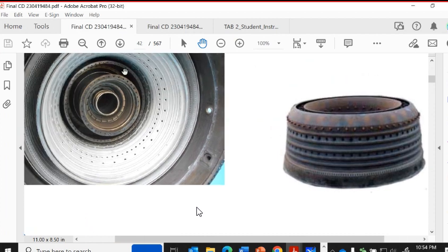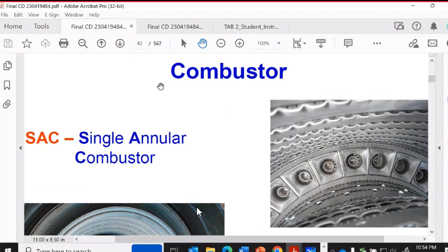My nozzles are up and through here. My airflow nozzles are right back there. But coming through here, I've got air also being forced on the inside of the combustor. And again, I've got holes through here as I hit against these raised lips. Kind of see it better through here. Instead of deflecting and going around it, it's going to go through the cooling hole.